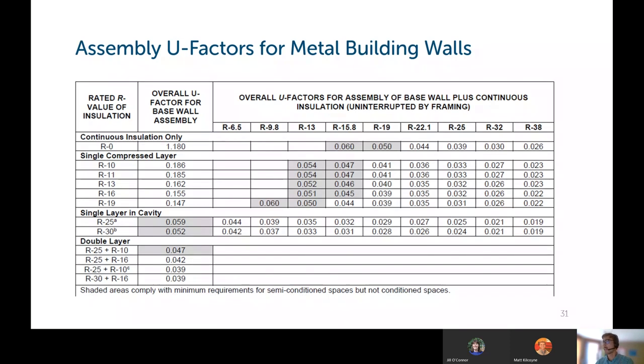This is another useful table in there for the assembly U factors of metal buildings, similar to the other tables we looked at, where you've got continuous insulation on the top, different amounts, and then different ways to insulate the walls for a metal building. Continuous, single, compression layer, cavity insulation, double layers. And you can plug your numbers into this and see where you come out. Again, gray is semi-conditioned and white is conditioned spaces.